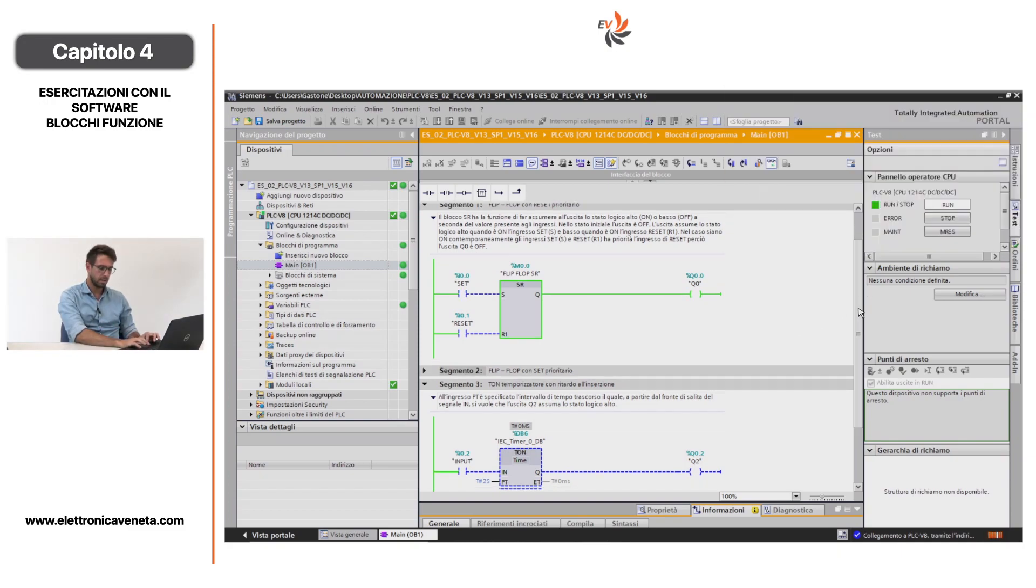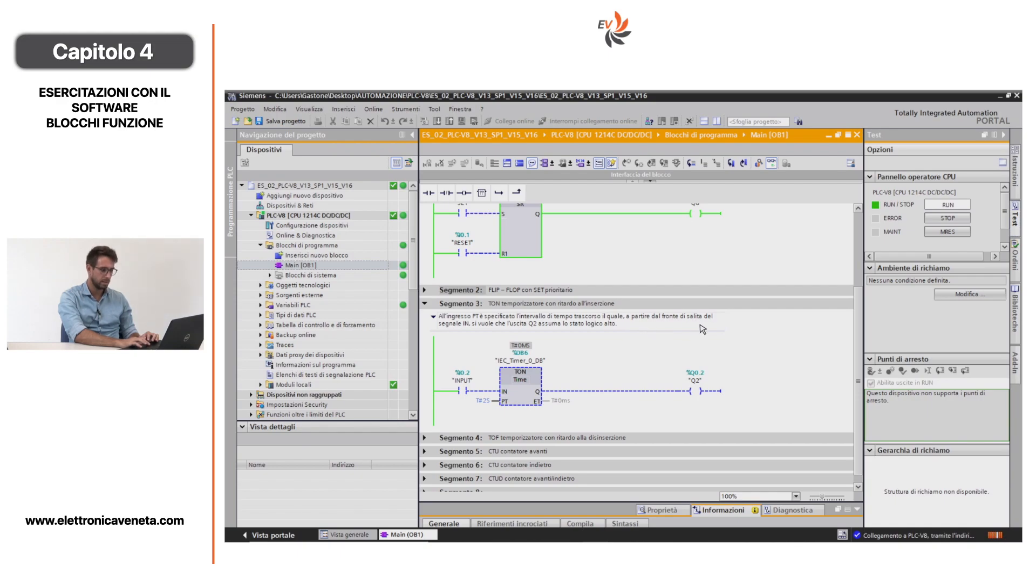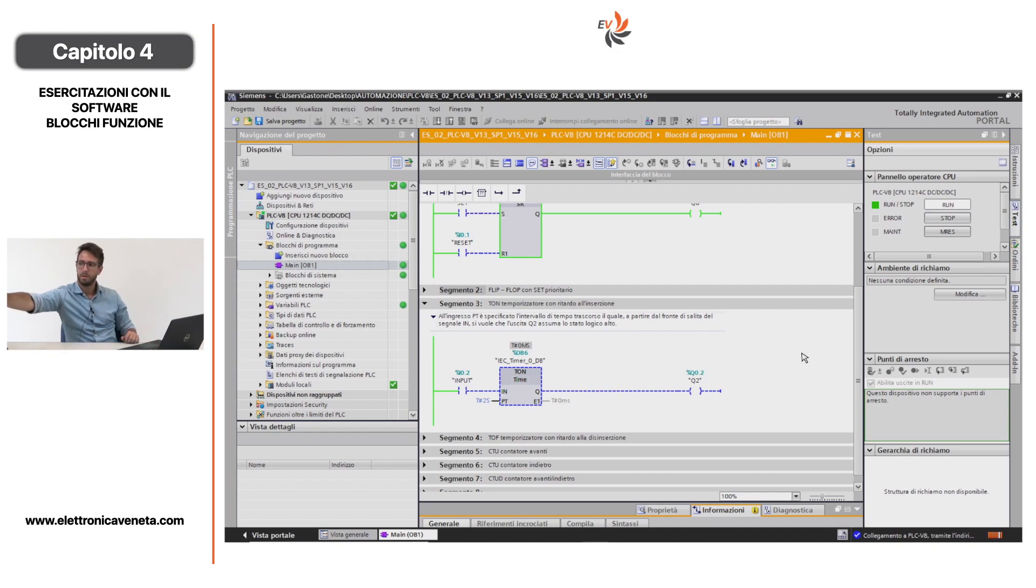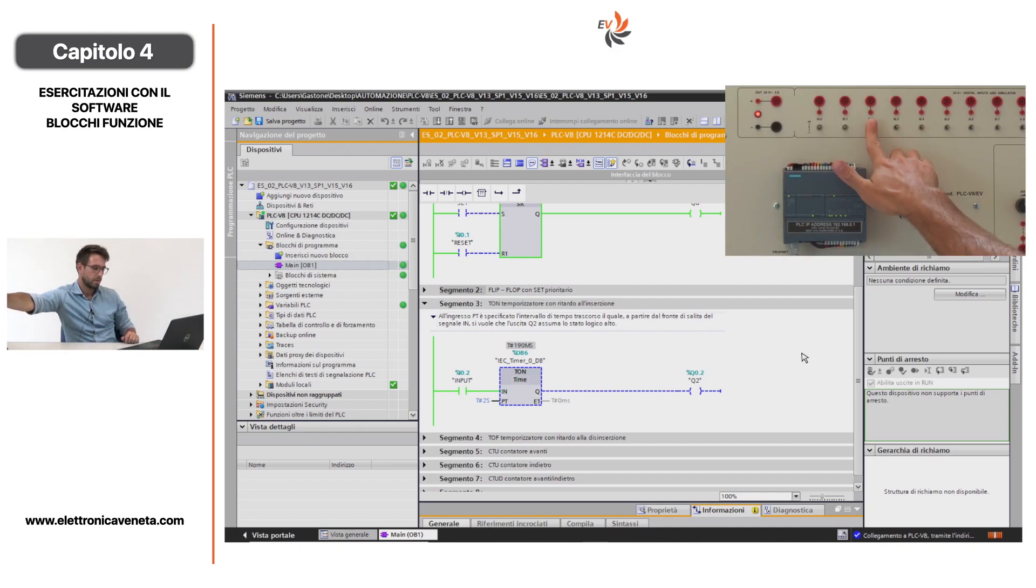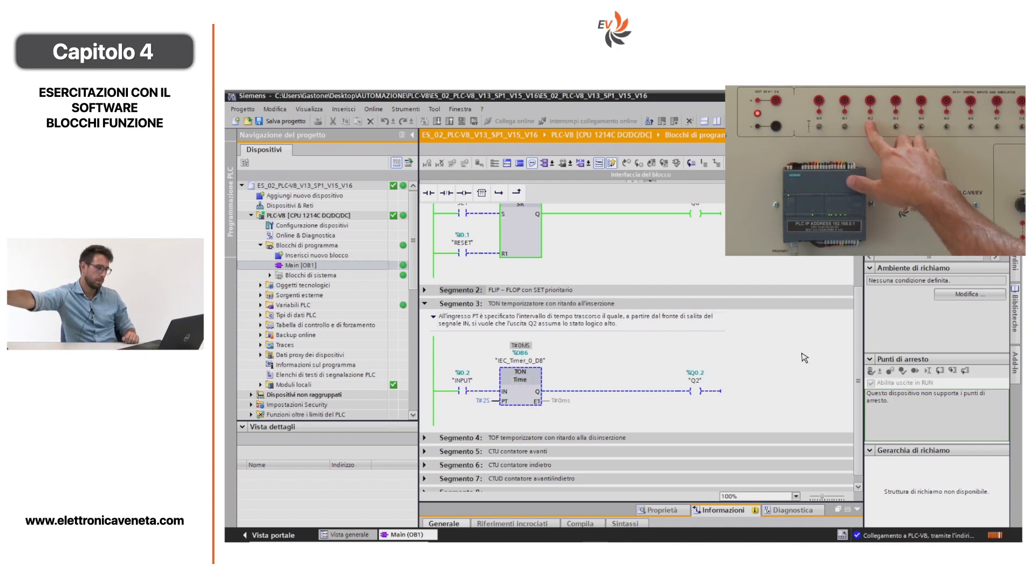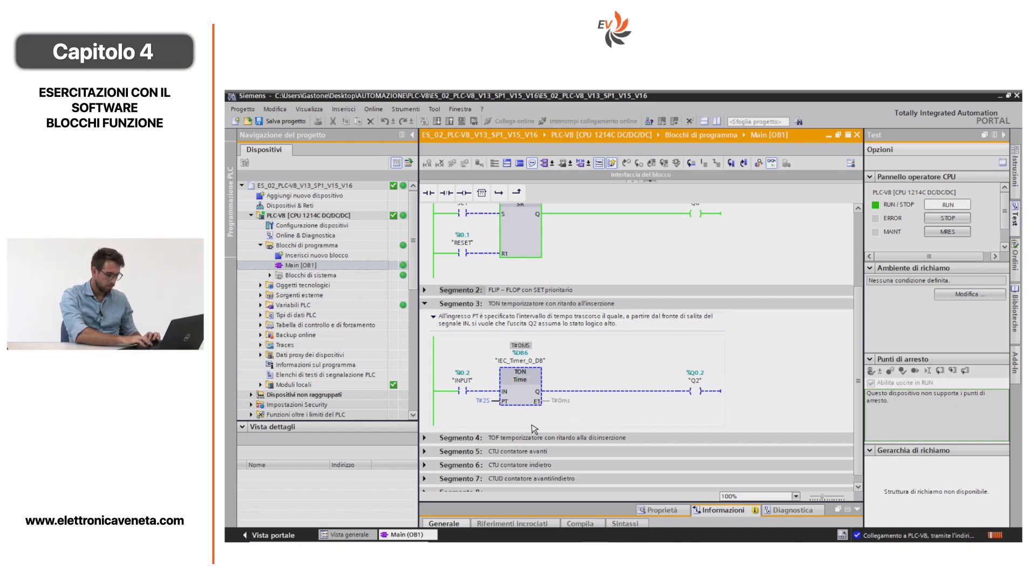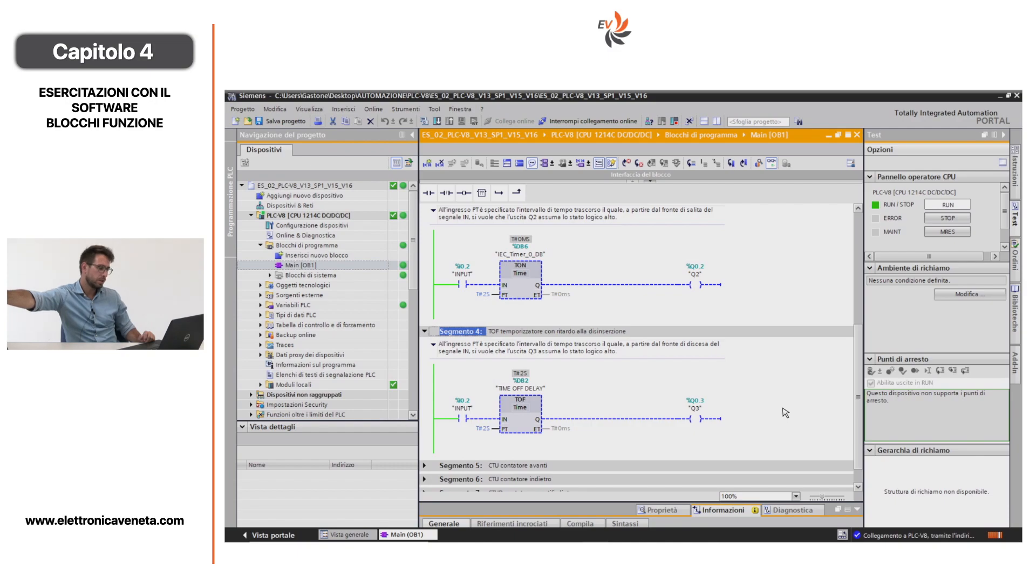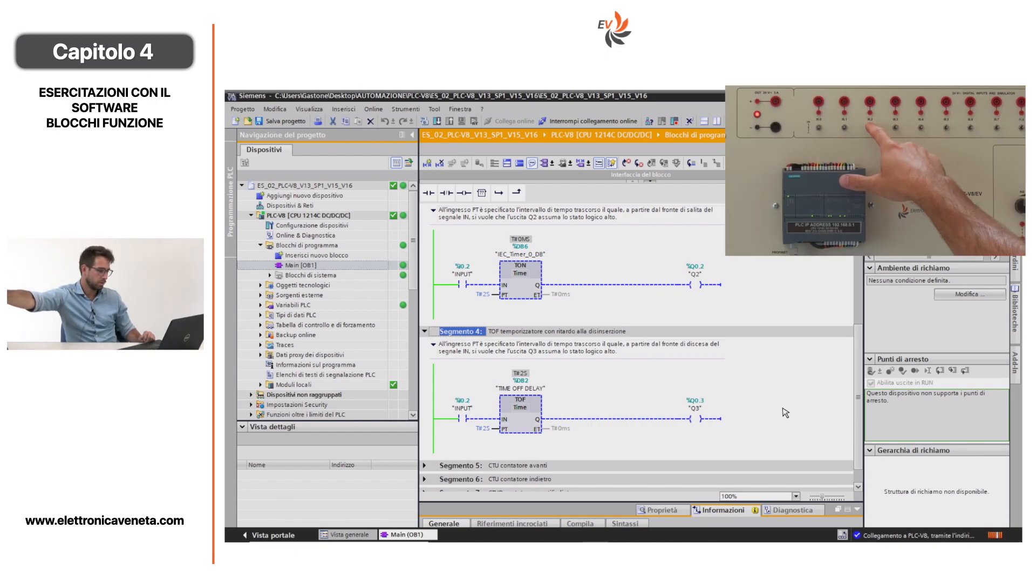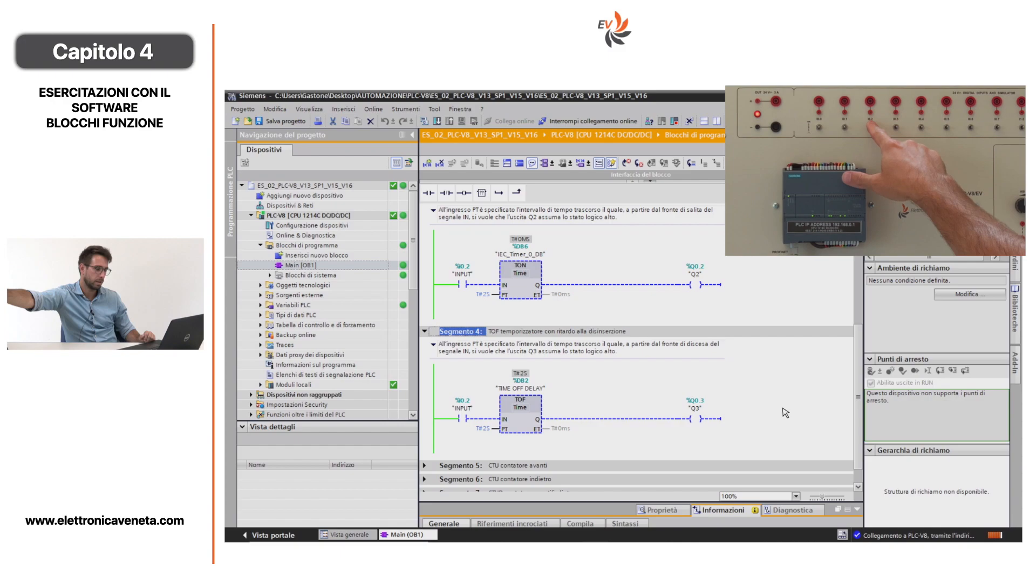Passiamo al segmento 3, dove abbiamo il blocco funzione temporizzatore, in questo caso un TON. All'ingresso PT è specificato l'intervallo di tempo trascorso il quale, a partire dal fronte di salita del segnale IN, si vuole che l'uscita Q2 assuma lo stato logico alto. In questo caso vado ad attivare I0.2 e solo dopo due secondi mi si abilita l'uscita digitale. Nel momento in cui naturalmente porto lo stato I0.2 a 0, non è abilitato Q0.2. Guardiamo il blocco TOF del segmento 4. Funziona al contrario. Per i primi due secondi dà un impulso, quindi l'uscita è abilitata.